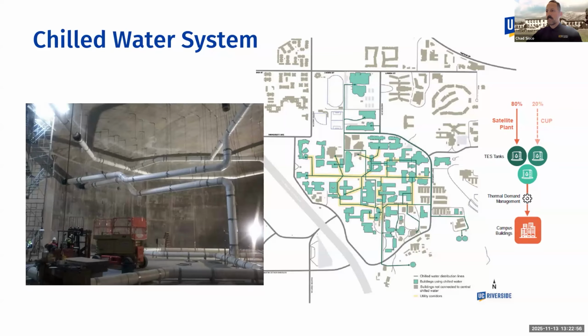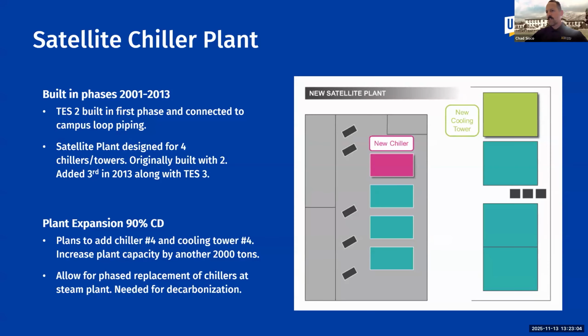So most recently, we completed the study to explore what it would take to decarbonize the campus, as everybody else did. So our next phase, excuse me, our next phase is to expand the satellite chiller plant once again. This is in alignment with our recently completed decarbonization study, which outlined the need to expand the satellite chiller plant in order to take equipment at the steam plant offline for future replacement, utilizing heat recovery chillers, heat pumps, and the like. We've almost completed this design. I think it's at 90% CDs for the 4th chiller and 4th tower. That'll bring the plant up to 8,000 tons of total chiller capacity.